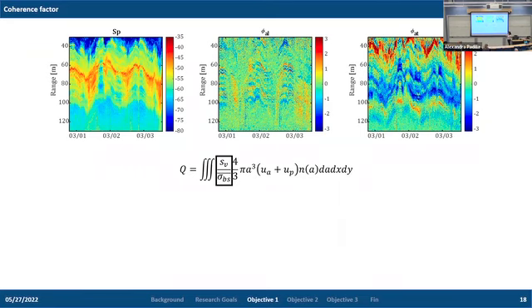We have this average sigma BS value, which is the average backscatter of a single gas bubble from the population of bubbles that we observe in the seep site. So this value, sigma BS, depends on the bubble size distribution of the seep site. We have the volume of the bubbles. We have this term here where UA is the rise velocity of individual gas bubbles and UP is any external rise velocity. So this can be from advection from the bubbles themselves or currents. NA is the bubble size distribution, and then we integrate all those values over the range of bubble sizes and the cross-sectional area that these plumes are intersecting.